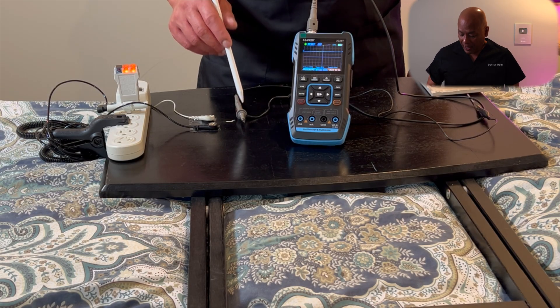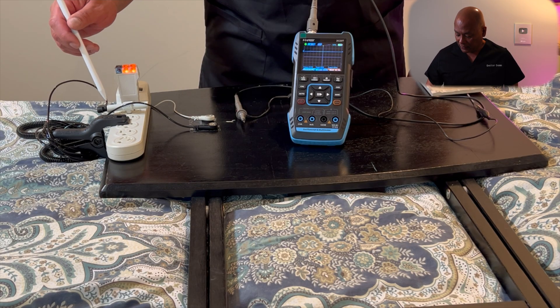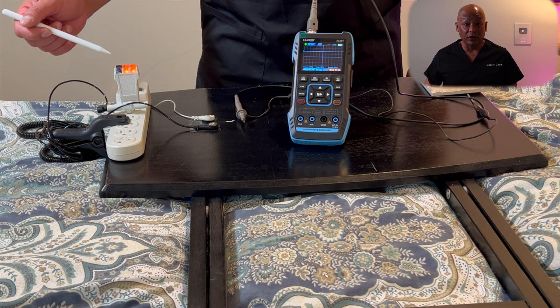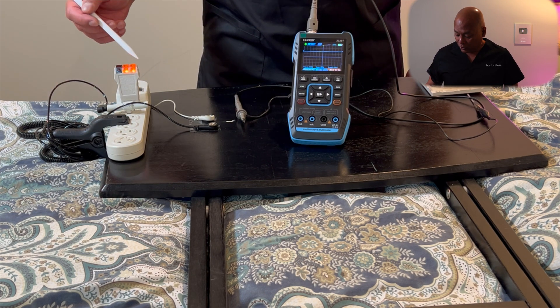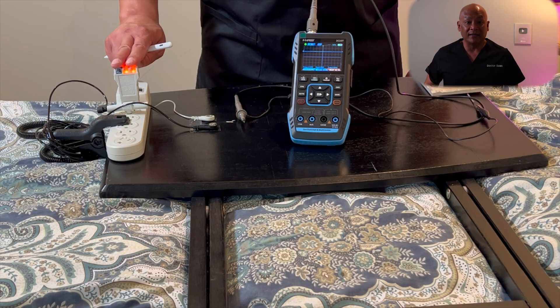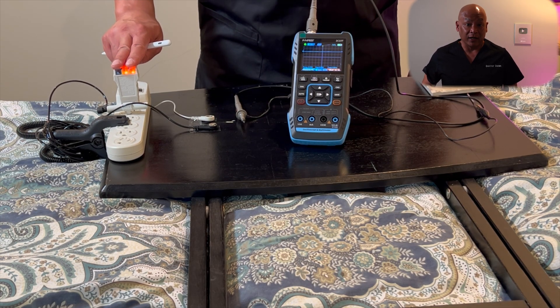This is the oscilloscope probe and I have two earthing cables here. One earthing cable is connected to this outlet ground, and you can see that this outlet strip is grounded because these two orange lights light up. However, the problem is these outlet checkers can fail a significant percentage of the time — they are not completely accurate.